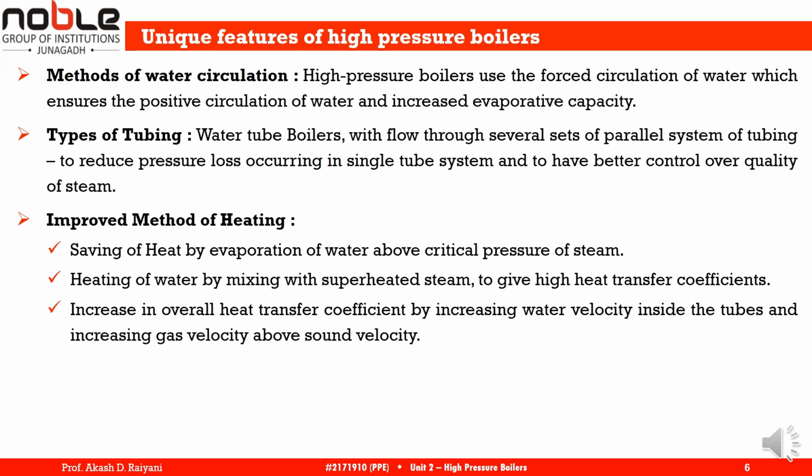Third one is improved method of heating. Here there is saving of heat by evaporation of water if we operate the boiler above the critical pressure of steam. Second, heating of water by mixing with superheated steam gives a higher heat transfer coefficient. There is also an increase in the overall heat transfer coefficient by increasing the water velocity inside the tube, and also by increasing the gas velocity above the sound velocity.